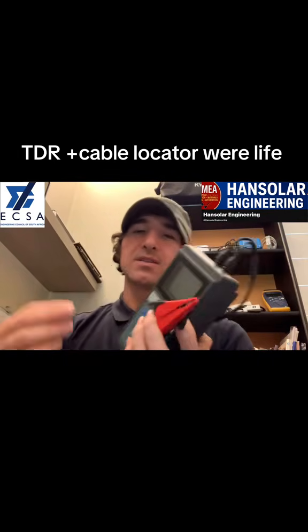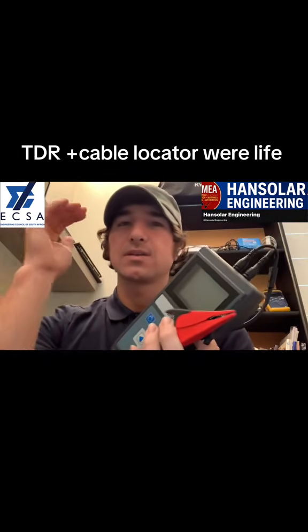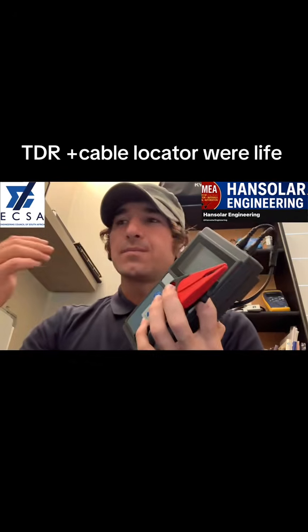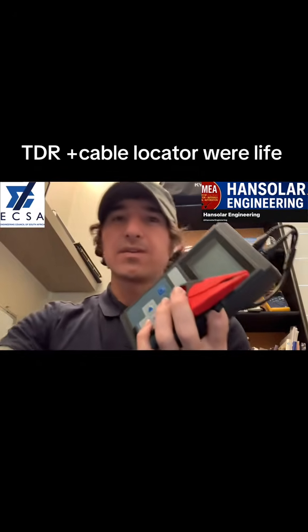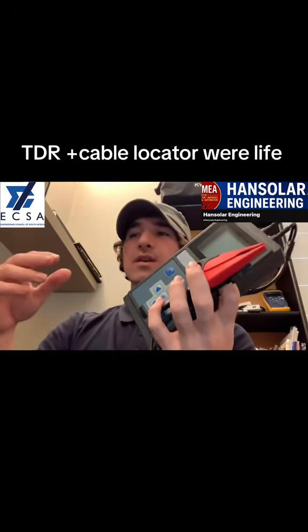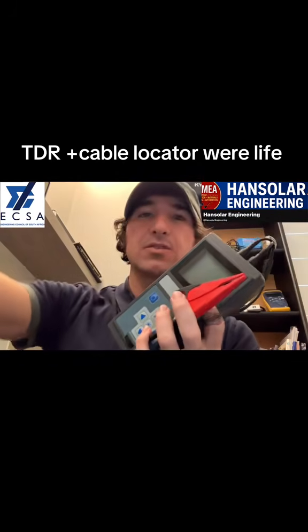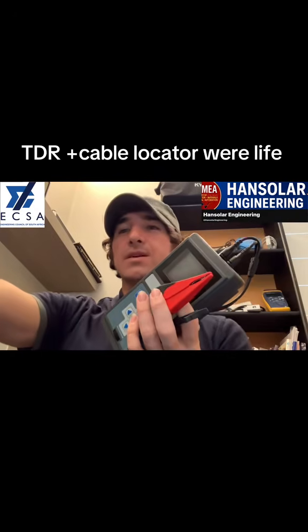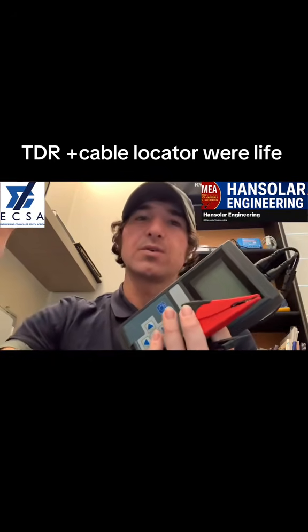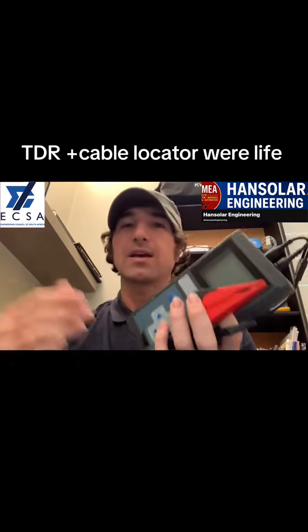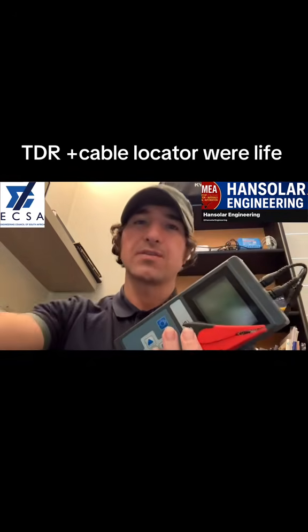So what it does is it sends a pulse, normally a step voltage, which sends an electromagnetic wave down a cable, and if it finds an open circuit, due to the fact that the wave propagates to the end of the cable, it has to reduce to zero. That in itself will send a wave back, and it'll time the wave and how long it takes, and it'll tell you where it found the disturbance.